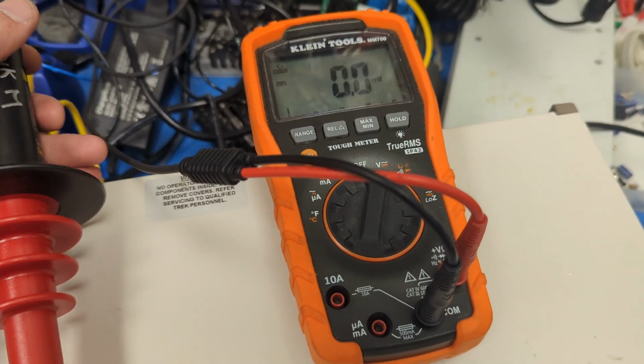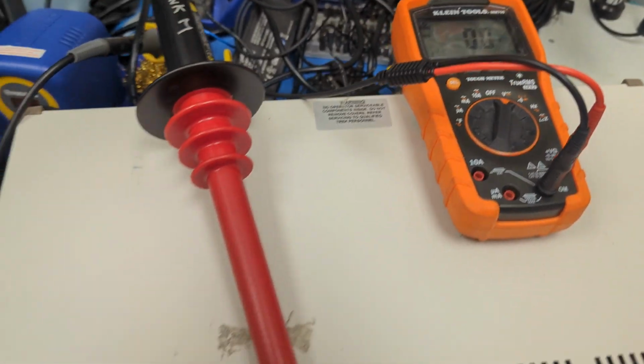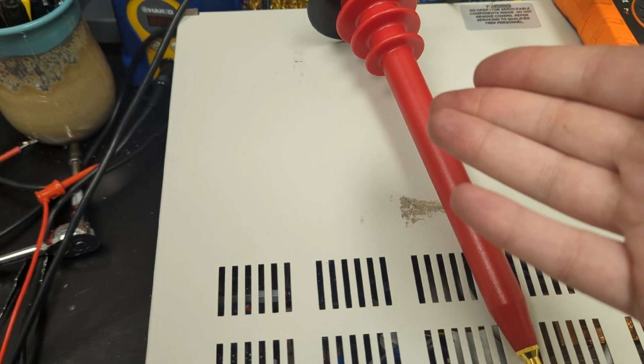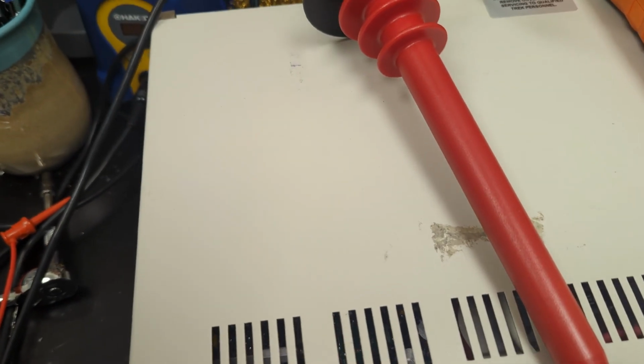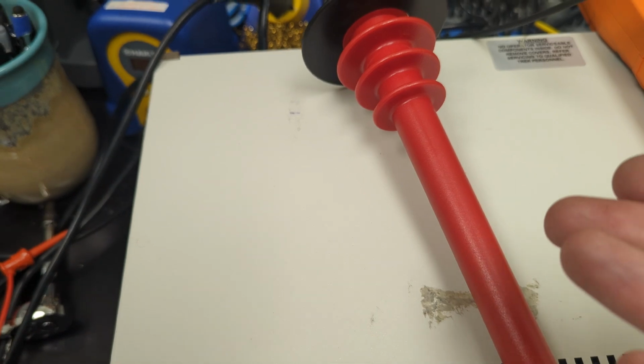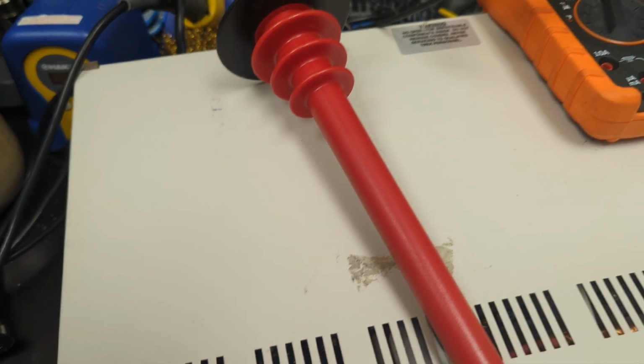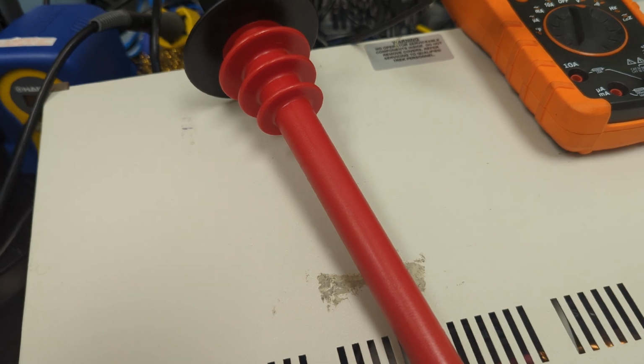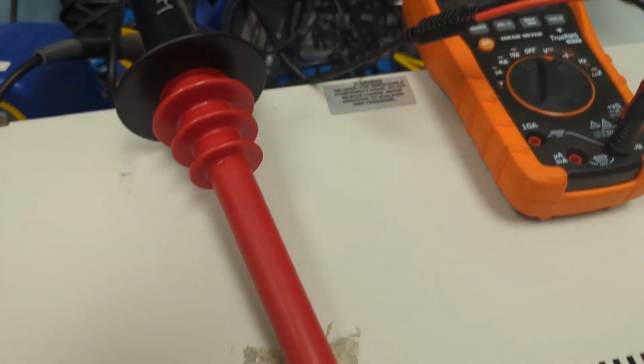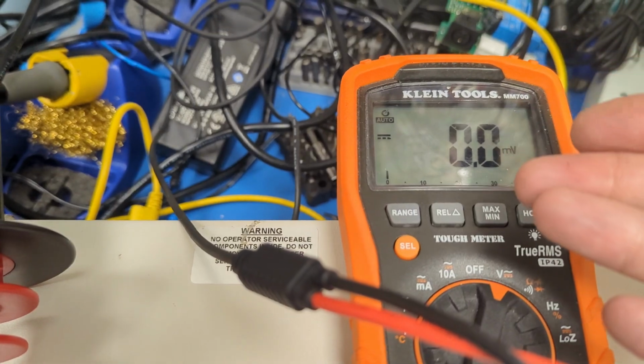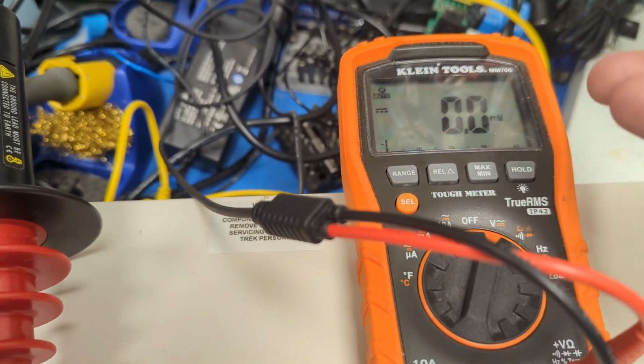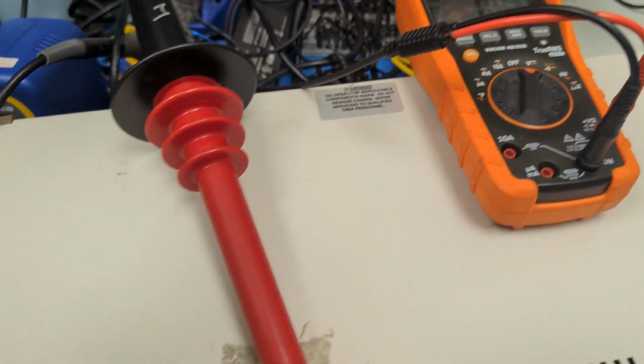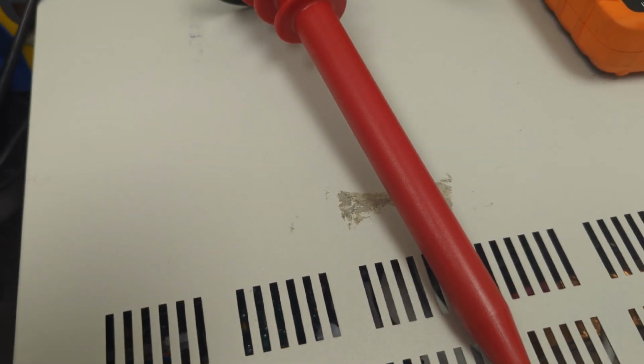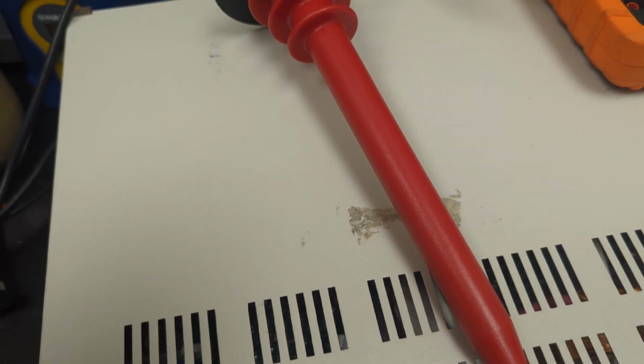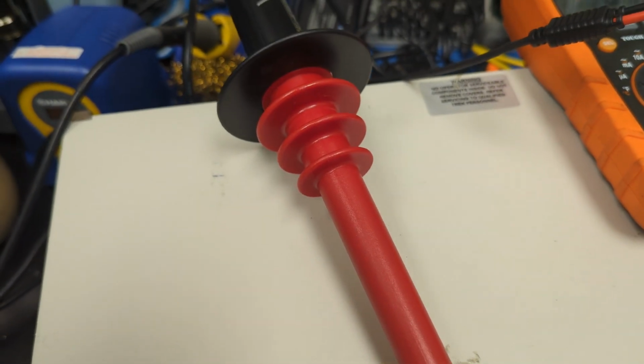Yeah, and so by the way, this is the high voltage probe. It has a series of resistors in there, which steps the voltage down 1,000 to 1. So instead of 10 kilovolts on the meter, you're seeing 10 volts. That's kind of how that works, so you can safely measure high voltages. You're not measuring that voltage directly, but yeah, very cool.